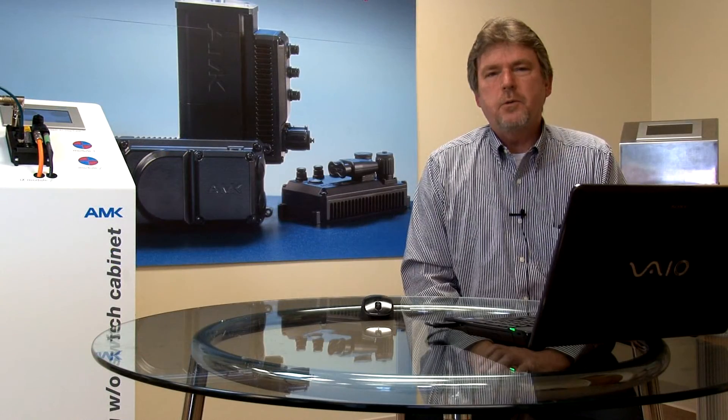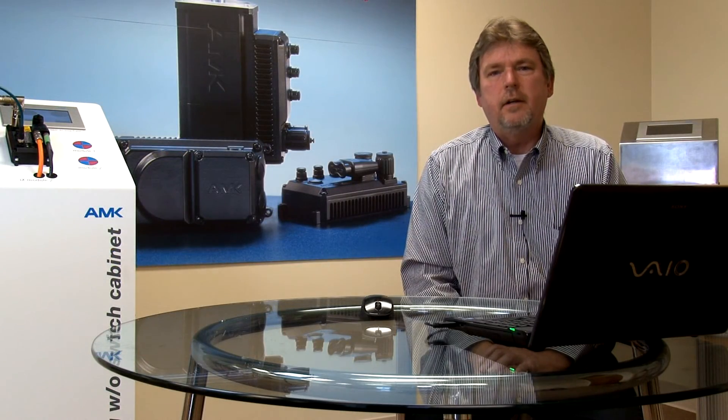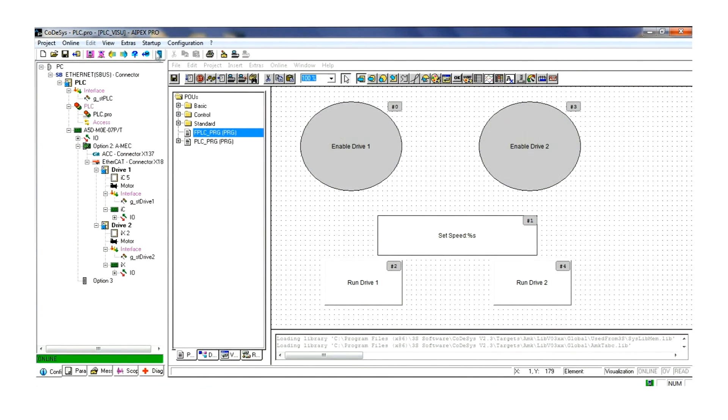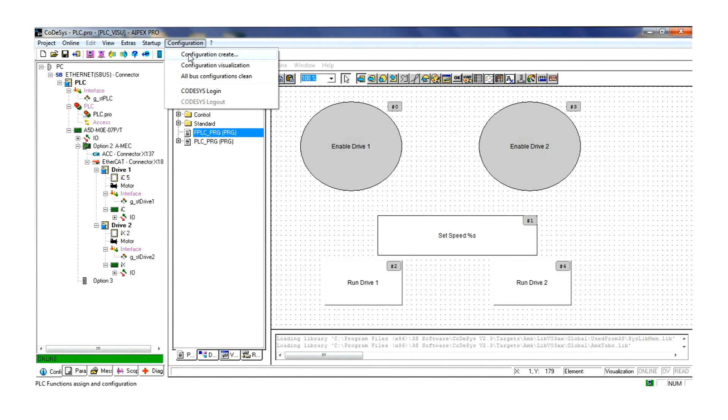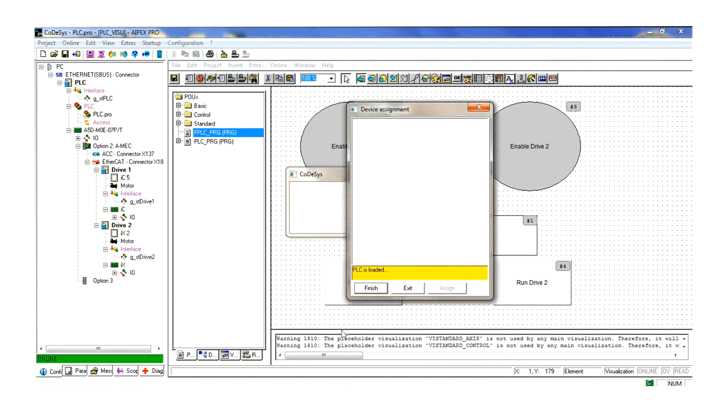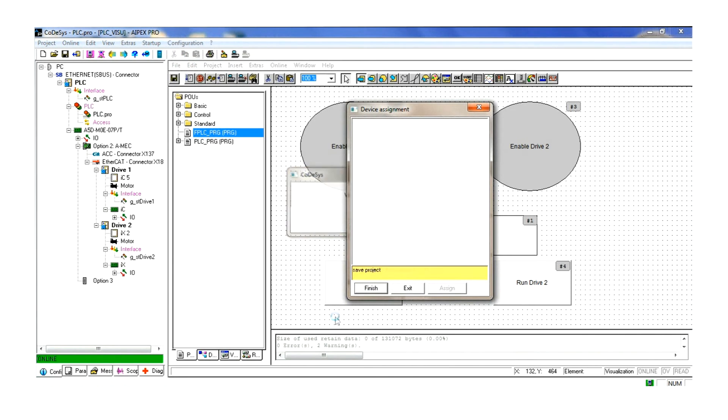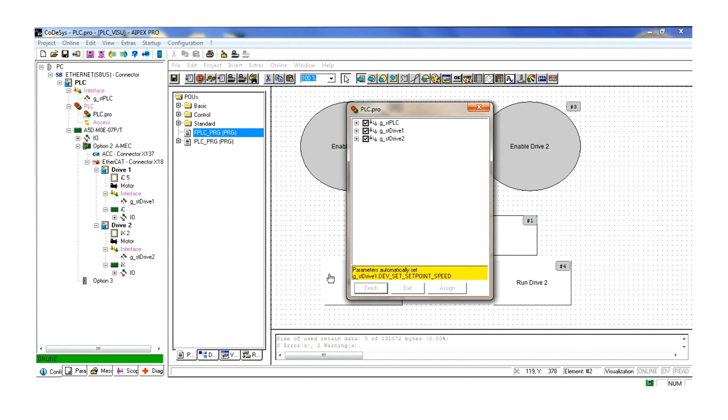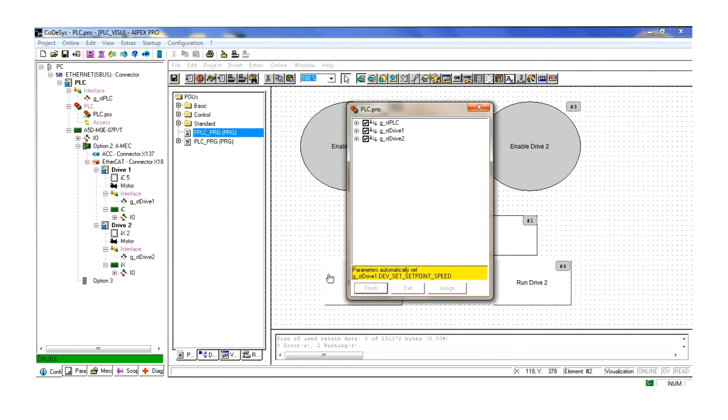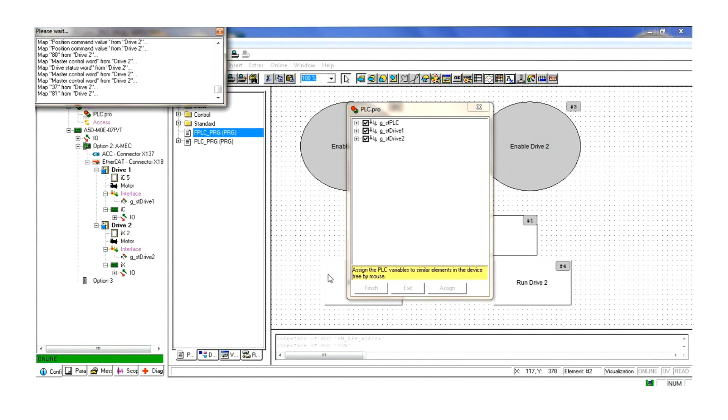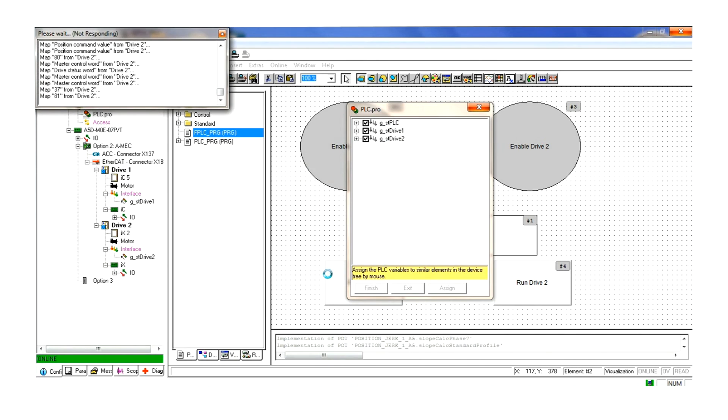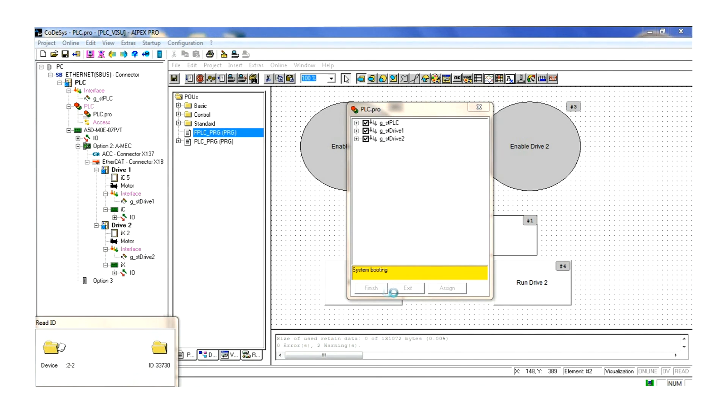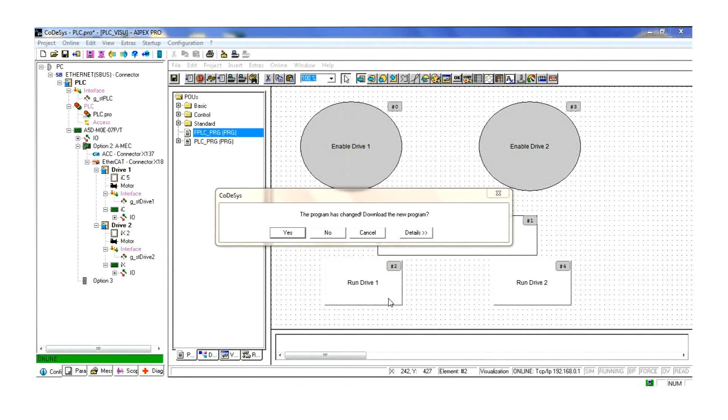Our other visualizations are created in the same manner. We are now finished with the programming. All that is needed now is to configure all of the messages for the drives and HMI. This is accomplished by choosing configuration create from the configuration menu. This sets up all communications between the controller and the drives as well as between the controller and the HMI. Then the program will be checked for errors, compiled, and loaded in the PLC.